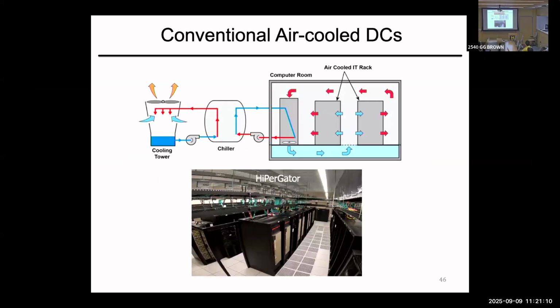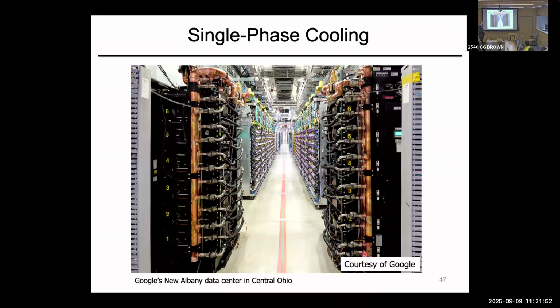The difficulty in data centers is that the prominent type, air-cooled data centers, uses a raised-floor architecture where cold air goes inside the racks, and then hot air gets out and goes to the air handling unit, then to the chiller and then the cooling tower, right? From a heat transfer point of view, you can see there's going to be a lot of thermal resistance at each interface, from chip to air, from air to liquid, all of these. So there are a lot of delta Ts. The industry is trying to address this and is doing so with liquid cooling. Years ago, nobody would have imagined that this would not look like a computer room, right? It's a mechanical room.